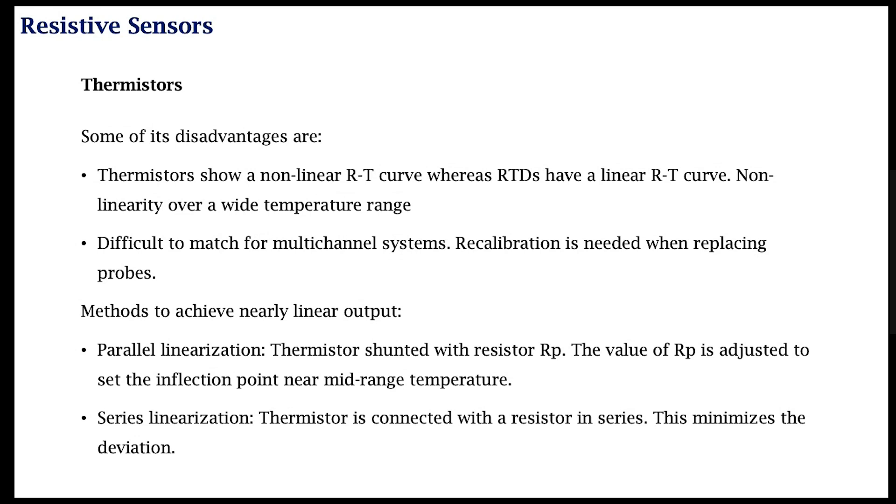Another approach is to have a thermistor in series with another resistor. This is another way in which you could increase the total resistance and thus change the deviation. But remember, all these things come with a cost too, because when you do this, you are also likely compromising on the sensitivity. So you need to make a choice on what is important for you in your measurement system. If a large range is required, you are looking at a particular application. If a relatively small range is required, maybe a regular thermistor will do the job for you.